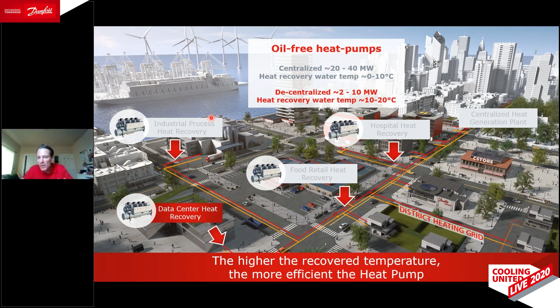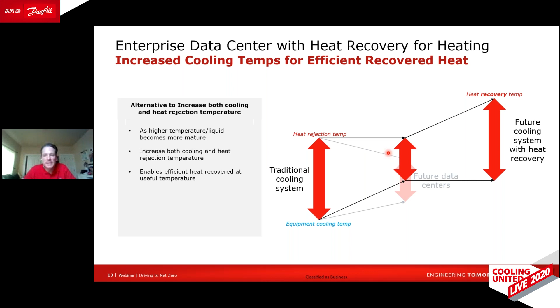So the summary here, shown with the example from the co-location data center, is that instead of moving to higher temperature cooling and keeping the heat rejection at the same temperature or lowering it, as in the enterprise case, you take that enterprise data center and increase the heating temperature so the overall differential temperature is roughly the same as the first generation data centers. You generate cooling with an air-cooled chiller at comfort cooling temperatures, but now, instead of just generating cooling, you're also generating the heating, capturing all that heat and supplying it to the district heating system—and generating all the revenue associated with this.